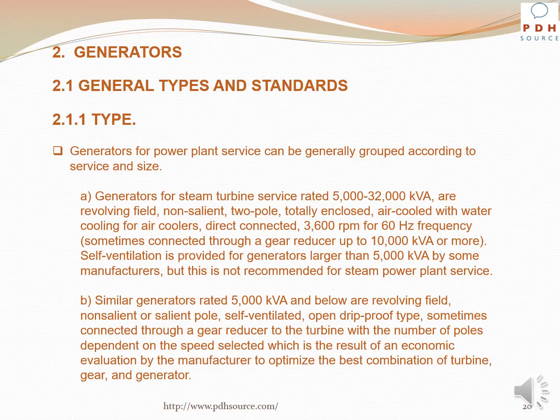Now, with regard to the generators, those for power plant service can be generally grouped according to service and size. Generators for steam turbine service rated 5,000 to 32,000 kVA are revolving field, non-salient, 2-pole, totally enclosed, air-cooled with water cooling for air coolers, direct connected, 3600 RPM for 60 Hz frequency, sometimes connected through a gear reducer up to 10,000 kVA or more. Self-ventilation is provided for generators larger than 5,000 kVA by some manufacturers, but this is not recommended for steam power plant service.